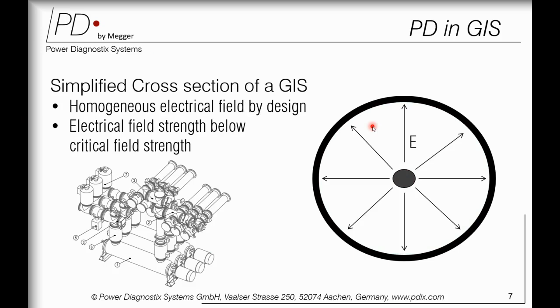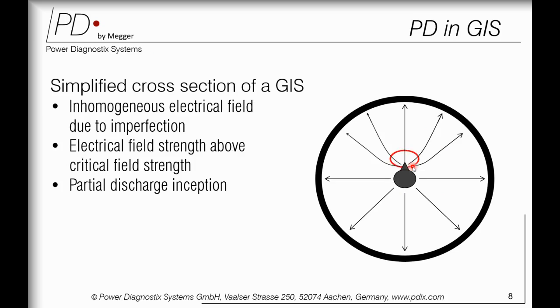So in this simplified cross section of the GIS, there is a homogeneous electrical field by design, where the electrical field strength is below the critical field strength. But due to some imperfection or some impurities, there will be an inhomogeneous electrical field, and this is the point where the electrical field strength goes above the critical field strength. So this is the point where you have partial discharge inception.